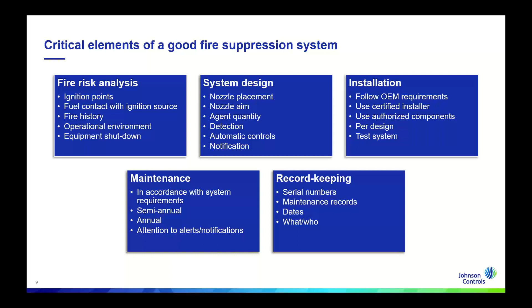Building off of that, there are industry standard codes and approvals that you can look for across the industry that will help to ensure that the fire suppression system meets all of those criteria. Some of those that you might look for are FM 5970, AS 5062, the NFPA standards 120, 122, 17, and 17A, MSHA certification, and CE markings. All of these bodies have additional standards and requirements that OEMs or vehicle suppression manufacturers are required to meet in order to produce the fire suppression systems.